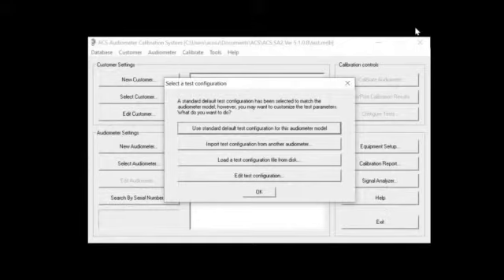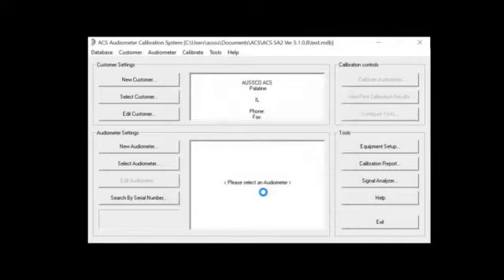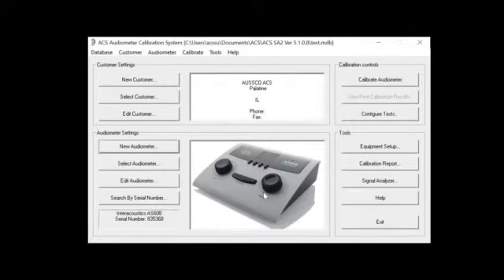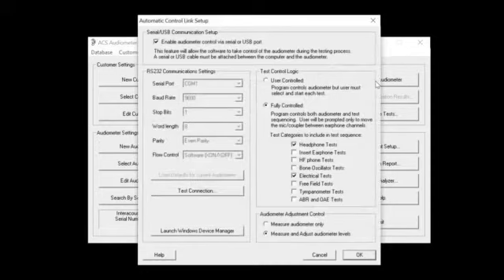Gives me the option, do I want to use the standard default test to calibrate this audiometer? You're going to use that 99% of the time. This is mostly used in the manufacturing facility. We can edit that test configuration. Again, you're taking control of the spaceship. Leave it alone. Click on OK. Only thing left for us to do, calibrate the audiometer. Click on Calibrate. Gives us some other selections that we can do.